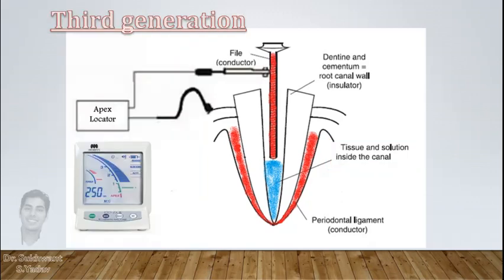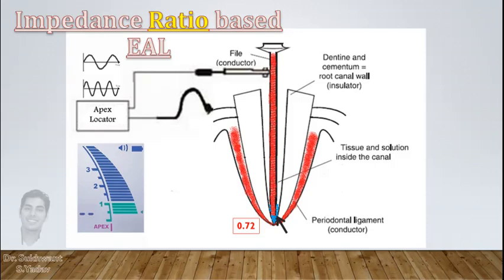To overcome this problem, third generation apex locators were introduced. In these devices, two different frequencies of current were used to record impedance. Now their impedance were compared and this ratio was found 0.72 at apical constriction in spite of any irrigant or any tissue present in the canal.